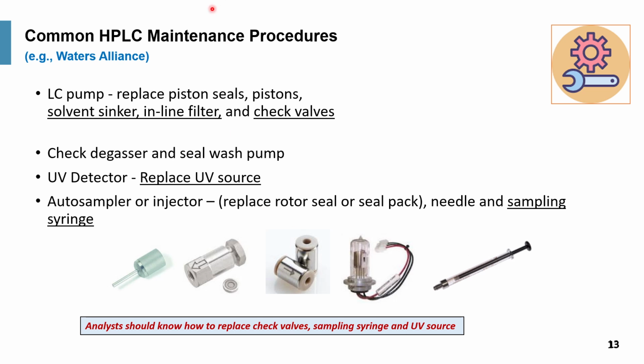Here are some common HPLC maintenance procedures. Once again, we focus on those that the analyst can do. For the pump, learn how to replace the piston seal, particularly if you have an older system, where piston seals tend to be less reliable. Replacing the solvent sinker or the 10 micron filter is very easy. These are actually the ones that you drop into your solvent reservoir. Also, inline filters are very easy to replace, and also check valves, particularly for the Waters Alliance system. Learn how to replace a UV source from a UV detector.